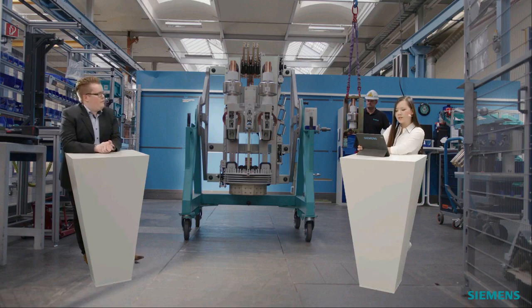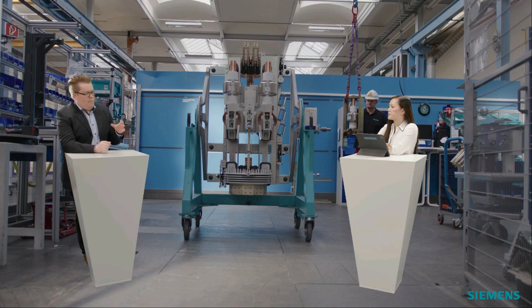Another question is, what is the impact of parallel generators at the same bus bar? Is it covered in this estimation tool? This is also not covered by the estimation tool, but it can be simply calculated. Important is to know the total amount of generated power. So let's imagine we have not only one generator, but maybe two, three, or four generators. We have to calculate each short circuit current of each generator.